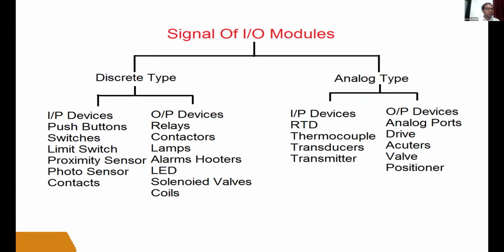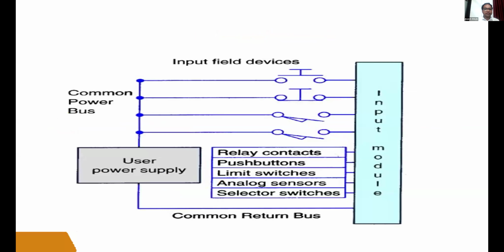In discrete IOs we can connect the push button, switches, limit switch, proximity sensor, photo sensor, contactor, relays, lamps, alarms, hooters, LED. And for all these components, just as I already told you how to do the connection of the sensor, in the same way a switch consists of NO and NC buttons. Easily we can connect these switches and sensors to the PLC if you have basic electrical and electronics knowledge. In the analog part, suppose RTD, if you want to measure the temperature, you need an RTD sensor, thermocouple, or thermistor. According to your need, we can connect the IOs. This is the simple diagram.